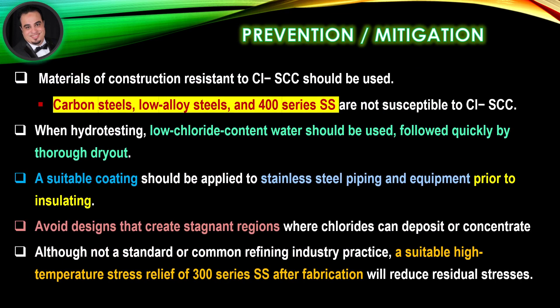Prevention and mitigation: Materials of construction resistant to chloride stress corrosion cracking should be used. Carbon steels, low alloy steels, and 400 series stainless steel are not susceptible to chloride stress corrosion cracking. When hydro testing, low chloride content water should be used, followed quickly by thorough dry out. A suitable coating should be applied to stainless steel piping and equipment prior to insulating. Avoid designs that create stagnant regions where chlorides can deposit or concentrate.